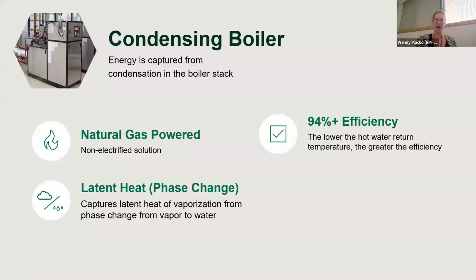Let's talk a little bit about the condensing boiler, which is a great gateway option. This option is generally with natural gas - you could maybe do hydrogen or other options, but typically it's natural gas. You get a lot better efficiency than a conventional fire tube boiler, going from 80% efficiency up to 94%, and it can get even higher, because the lower your return temperature, the better your efficiency gets. They achieve better efficiency by capturing some of the heat that comes out in the stack - the latent heat, which is the heat that goes into the phase change - by capturing the condensation on the boiler.